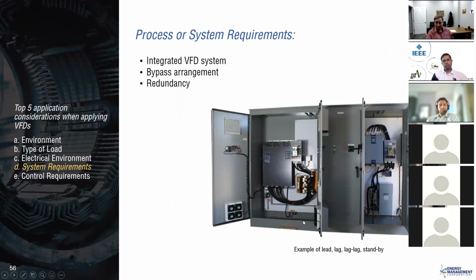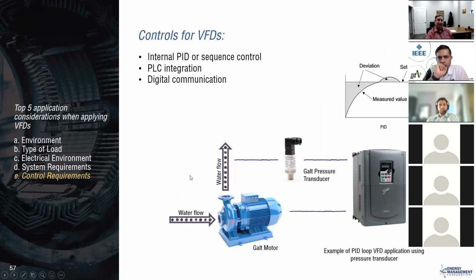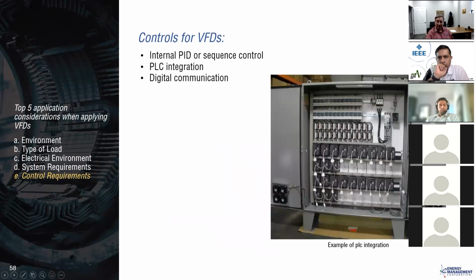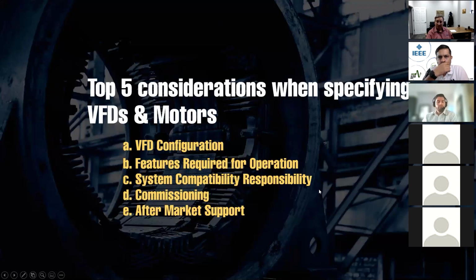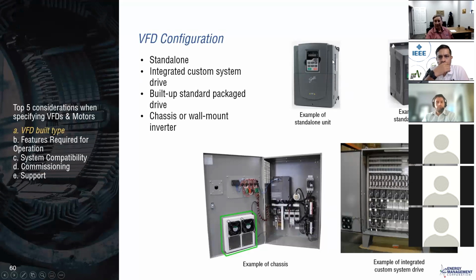Process control, this again is a lead lag type of system, where you can get into redundancy and all kinds of things when you apply VFDs that you would want to put together. And controls: the most common control obviously is a PID loop with a standard pressure controller. But this is for a potato processing plant where it's completely PLC controlled and tied back to a SCADA system. I hope I'm not going too fast here, but when specifying VFDs, this configuration is acceptable as a minimum standard to put on a wall, but there's lots of reasons to consider a packaged approach, and that's what we're really good at.